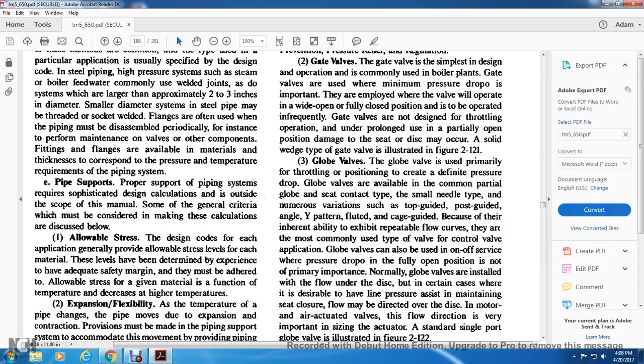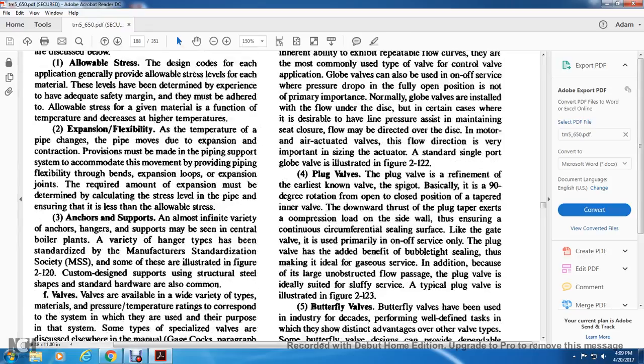Globe valve. The globe valve is used primarily for throttling, to create a definite pressure drop. Globe valves are available with numerous variations, such as top guide, post guide, angled, Y pattern, fluted, and cage guided. Because of their inherent ability to exhibit repeatable flow curves, their most common use is as control valves. Globe valves can be used in on-off service where pressure drop in the fully open position is not of primary importance. Normally, globe valves are installed with the flow under the disc, but in certain cases flow may be directed over the disc. The flow direction is very important. A standard size single port globe valve is illustrated in Figure 2-122.